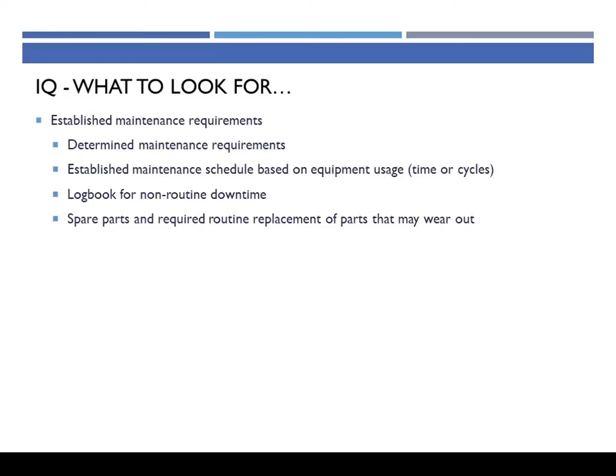Common problems we see during the IQ phase are that companies just don't verify all their activities. They don't verify that they hooked it up to the utilities, or that they put it in the maintenance or calibration program. If you don't have a record showing it entered the maintenance program, you can't prove you did it. So you have to provide the records. Remember, that's part of the FDA's expectation that you've established a procedure.